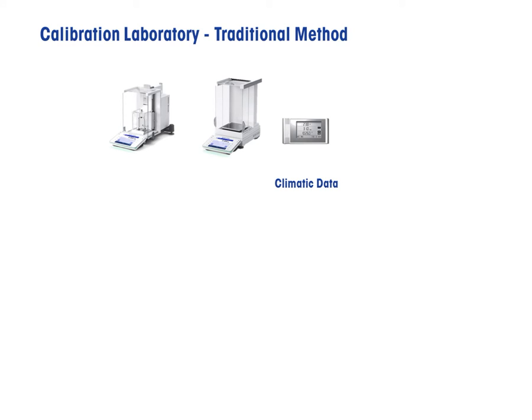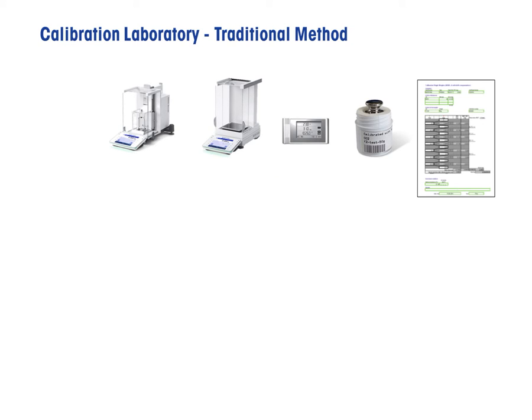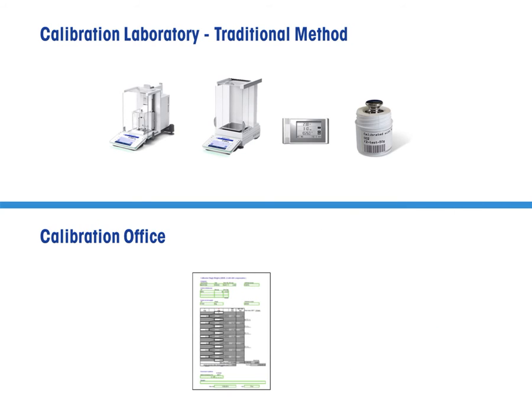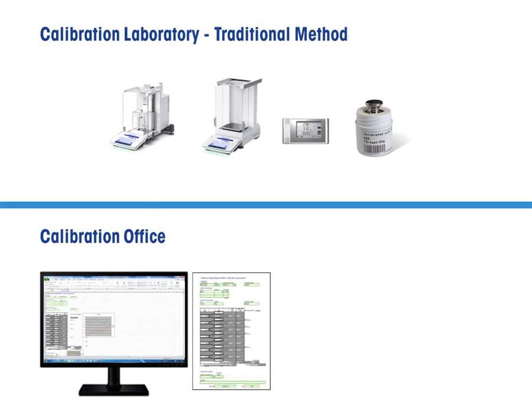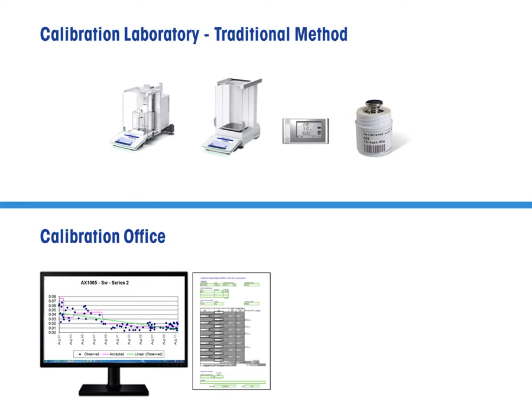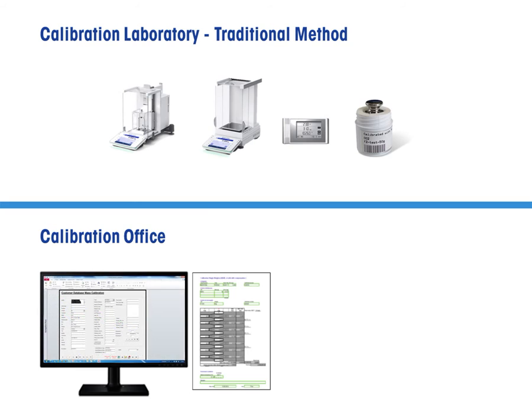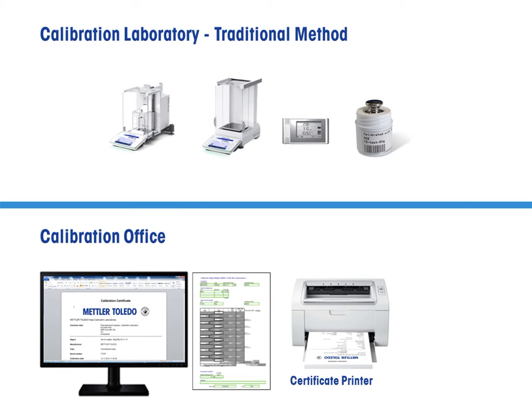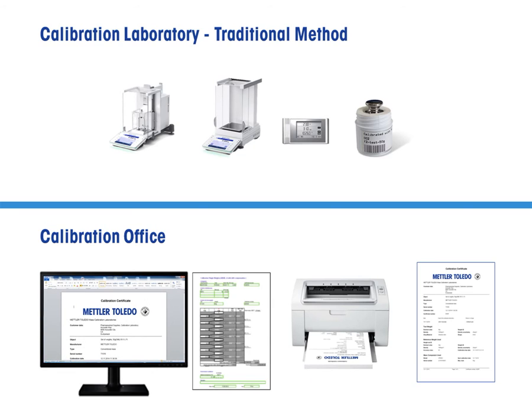Traditional mass calibration requires a mass comparator, climate sensor for air density calculation, and spreadsheet templates to record the measurement data. The completed template is taken to the office, and data is transferred to the computer spreadsheet to calculate intermediate results. The intermediate results are imported or transcribed to another database system, and the certificate is generated. After detailed analysis of the certificate content, it can be printed and signed off by the calibration manager.